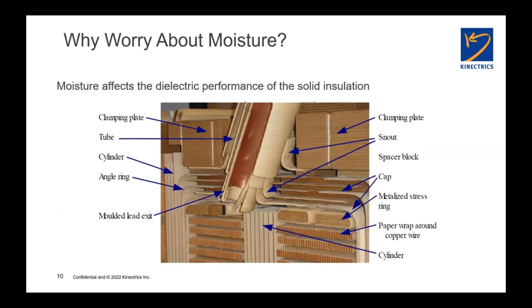For those of you that may not be familiar with the internal guts of a transformer, this is a cross-sectional view of a high voltage winding arrangement. Basically, what I tell folks is that everything that's brown in this picture is cellulose insulation material. You can see inside this lead exit tube here, we can see the copper that comprises the conductor that would be going up to the bushing. And of course, in the winding itself, we see the rectangular copper wires, but even these are individually wrapped with cellulose based paper wrap. And we see all different manner of components here.